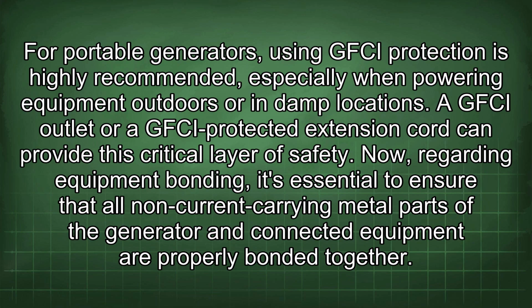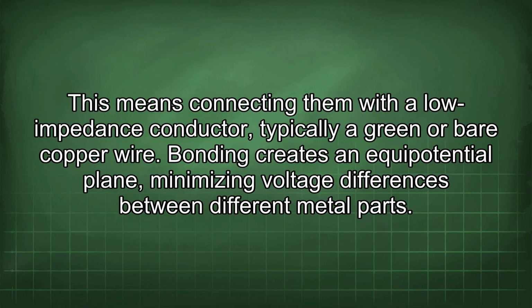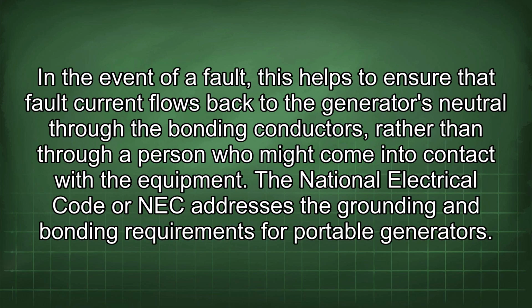Now, regarding equipment bonding, it's essential to ensure that all non-current carrying metal parts of the generator and connected equipment are properly bonded together. This means connecting them with a low impedance conductor, typically a green or bare copper wire. Bonding creates an equipotential plane, minimizing voltage differences between different metal parts. In the event of a fault, this helps to ensure that fault current flows back to the generator's neutral through the bonding conductors rather than through a person who might come into contact with the equipment.